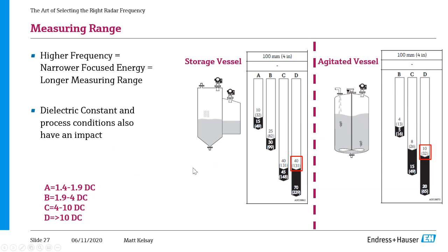Go next. We look at what effect process conditions have on the measuring range. So now we're comparing the storage vessel to the agitated vessel. This is the same style of radar, same size of horn. Because of that turbulent surface, we're no longer able to measure that lowest dielectric range at all. So we only start with the B, and if you look at even water in an agitated vessel, we're able to measure about 32 feet. However, in just a storage vessel, again, it's 131 feet. So you can see what a turbulent surface does to your measuring range as well.